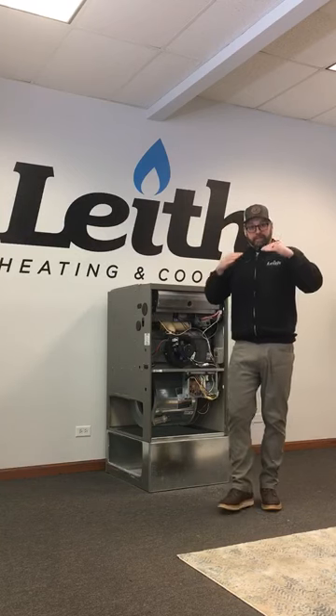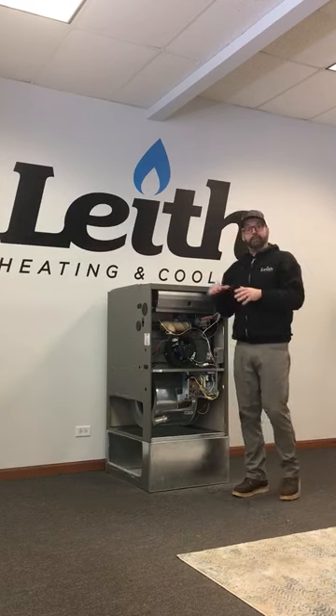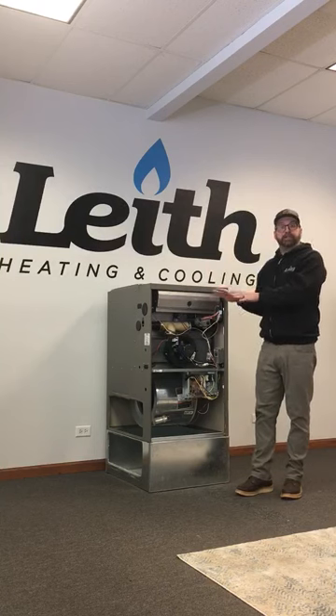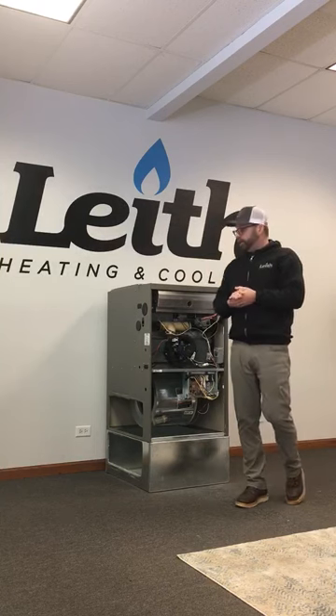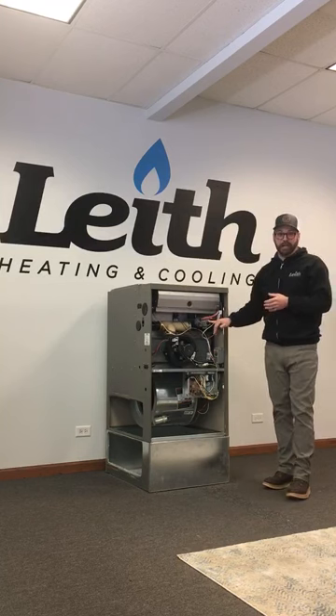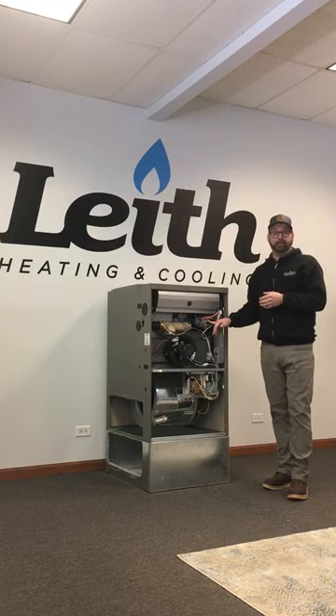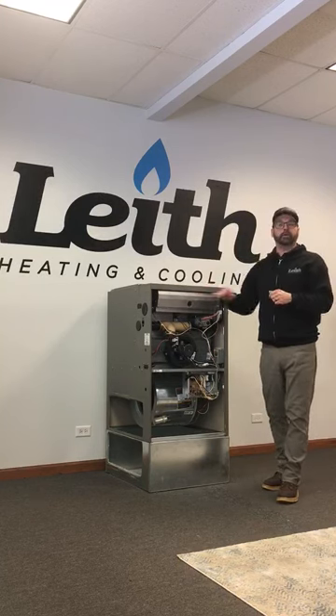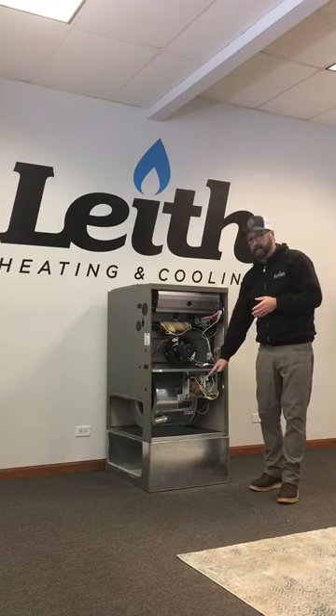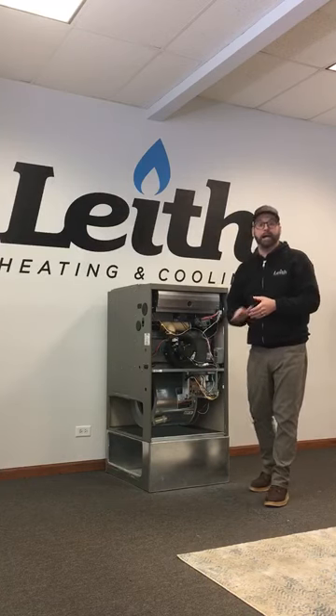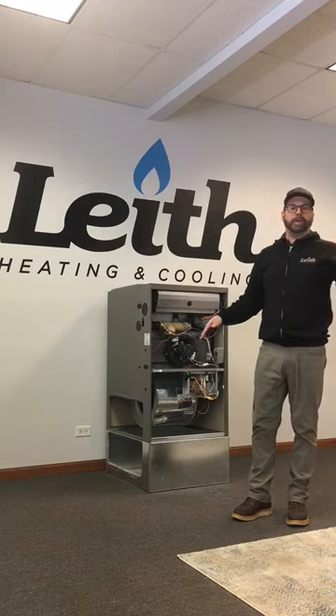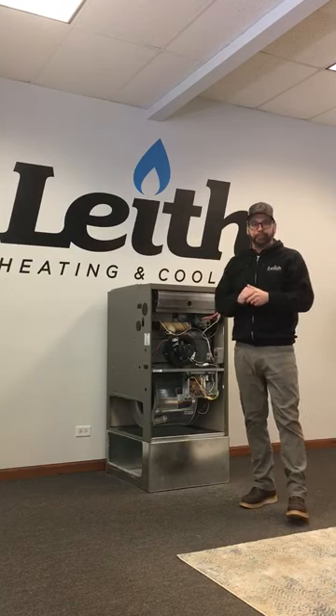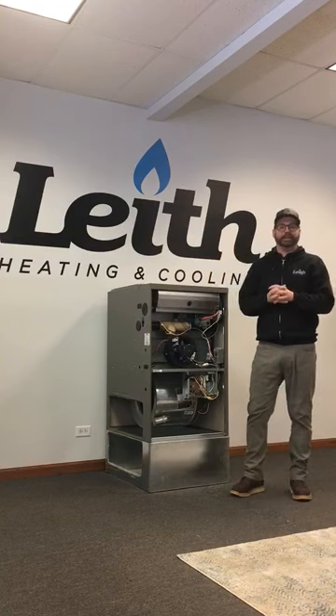Now once the home is warmed up and the thermostat is satisfied, it will then disconnect the call for heat, and the furnace will start a sequence in which it is going to shut down. The first thing it will do is de-energize the gas valve. The gas will stop flowing, the burners will go out. The ICM module will then start a timer in order to shut the blower down. Now that could be anywhere from 60 to 90 to possibly 120 seconds.